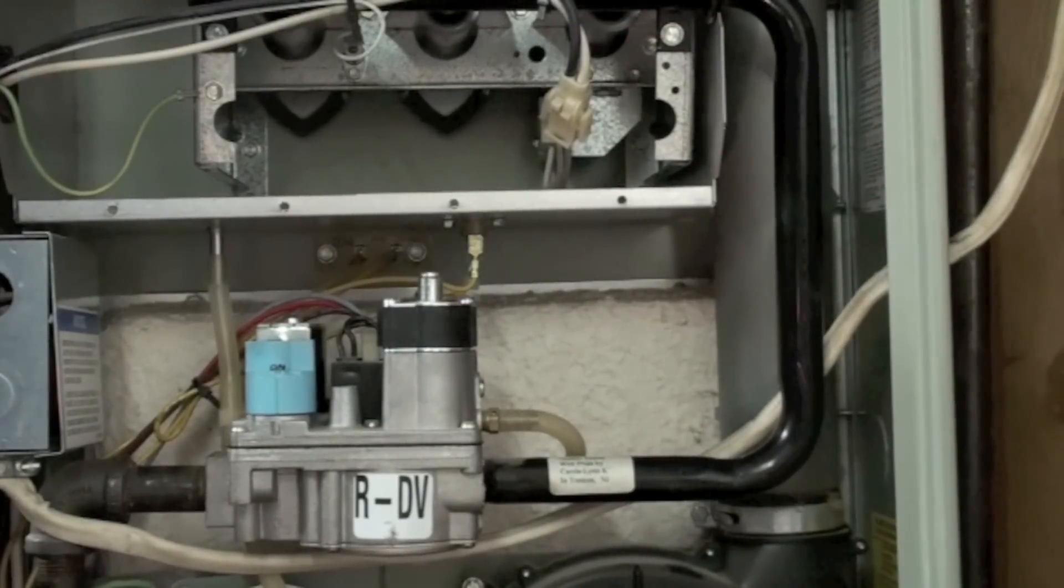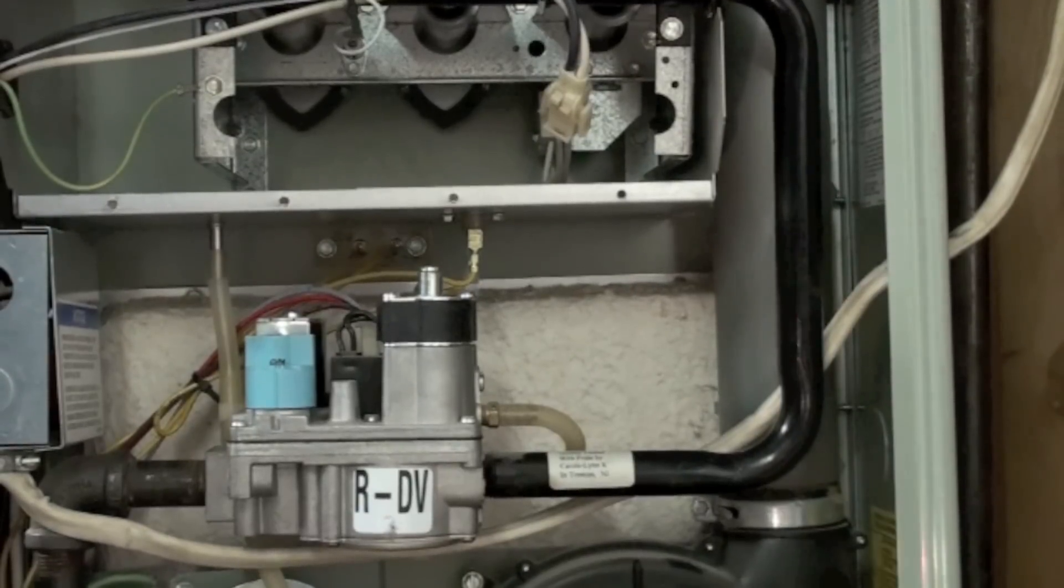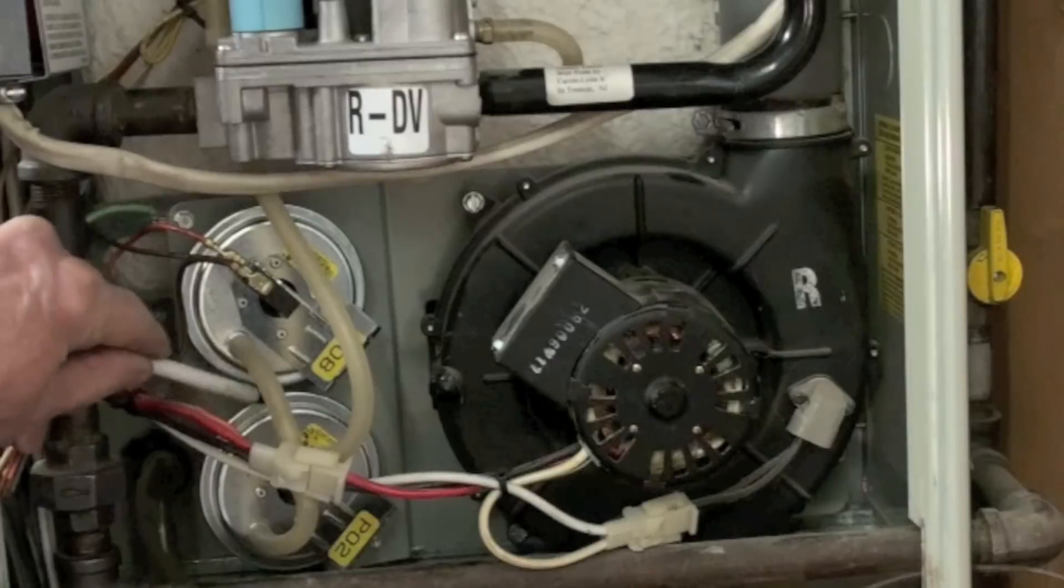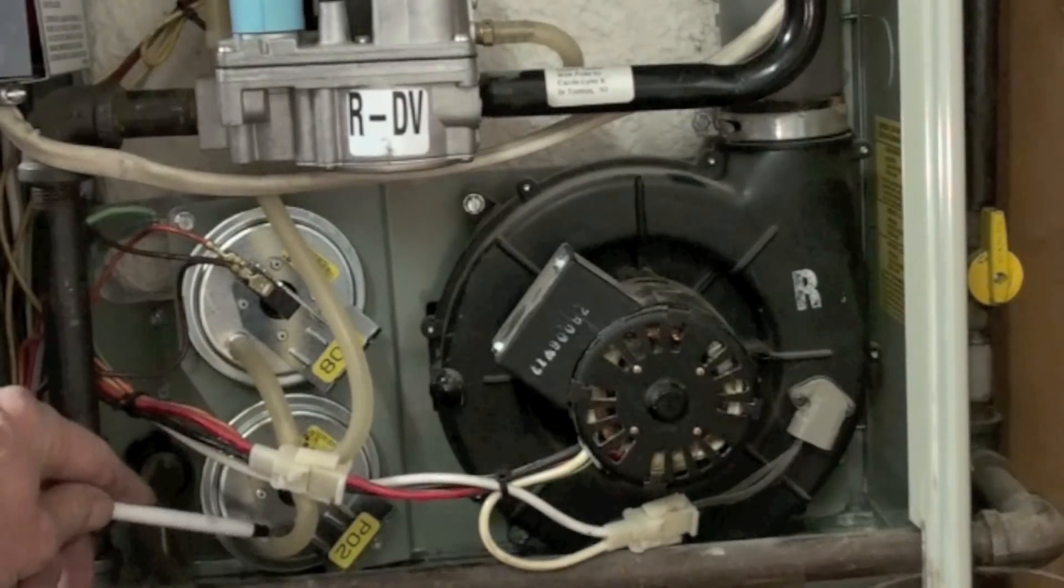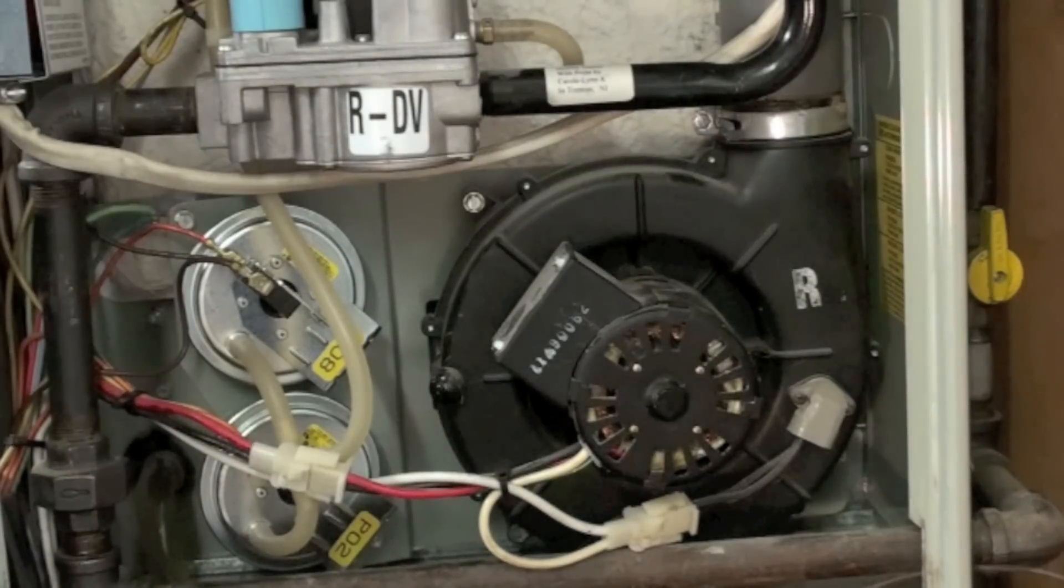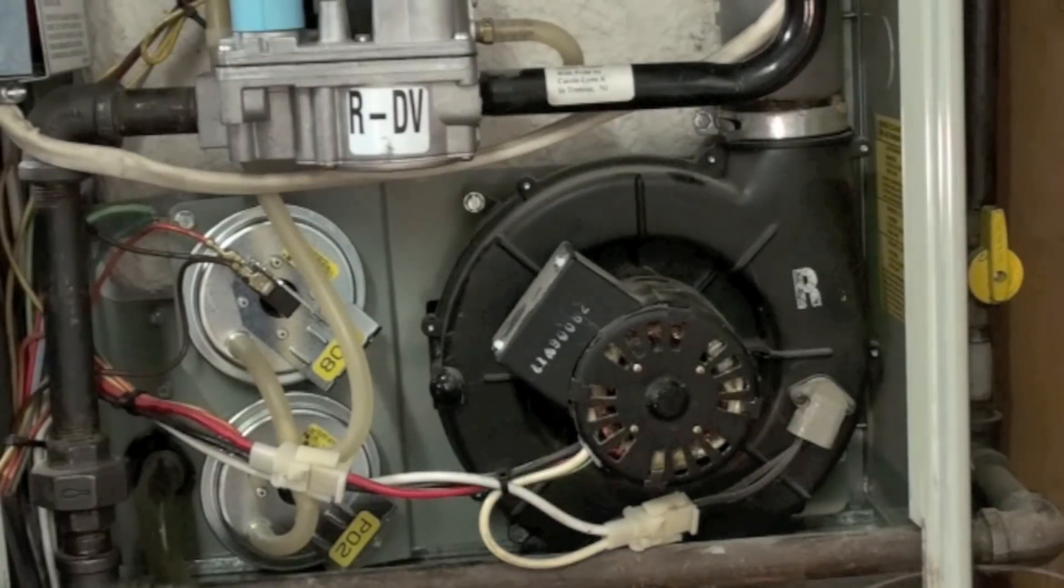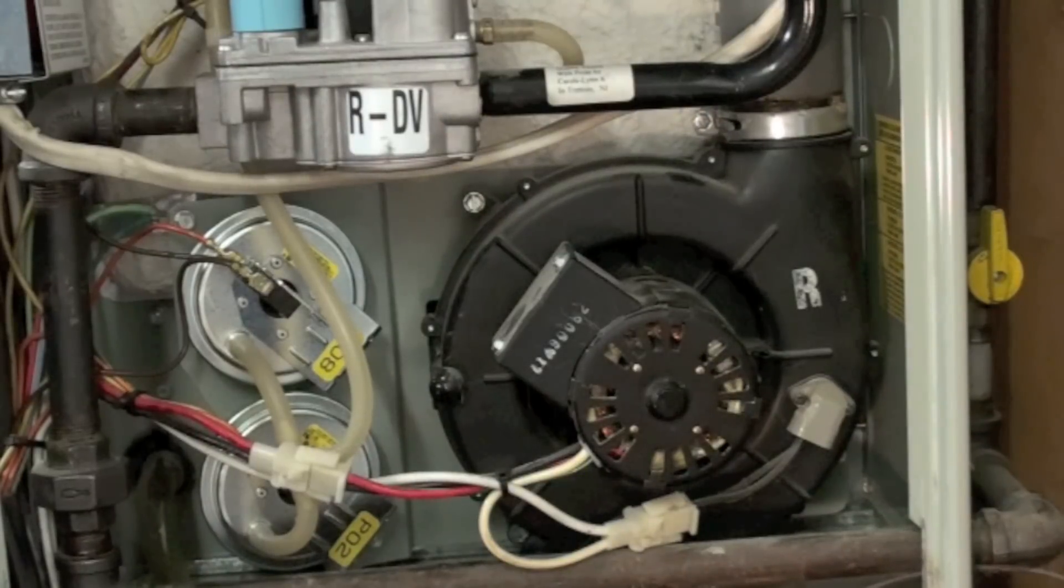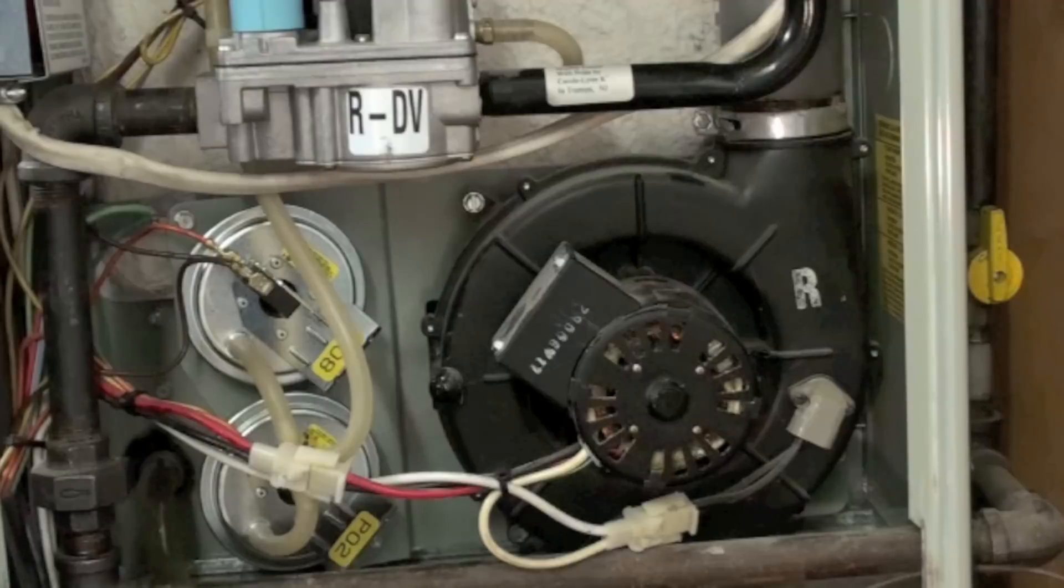Okay, things other than flame failure problems that could cause short cycling. Pressure switches, maybe this tubing here is looped down and got water in it or actually the pressure switch itself has got water and that'll cause it. That's usually a low ambient condition like it's very cold in the house. That might happen then.